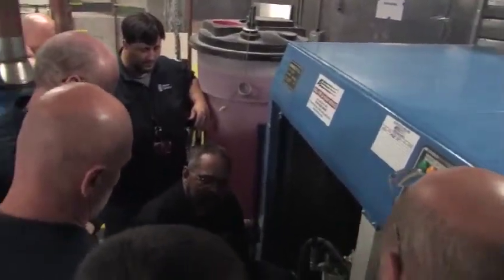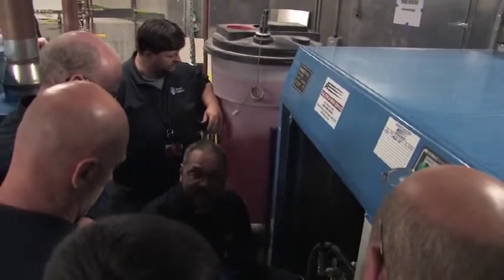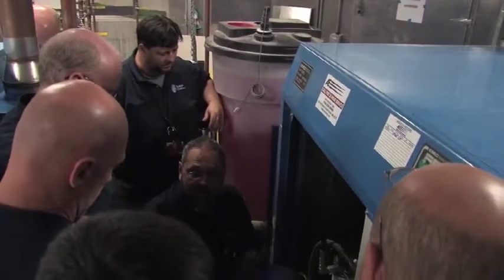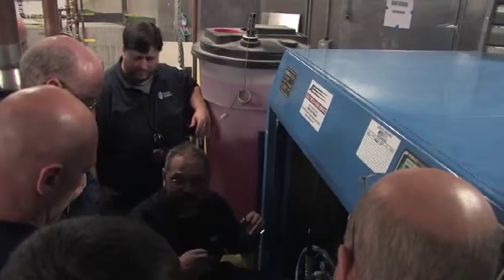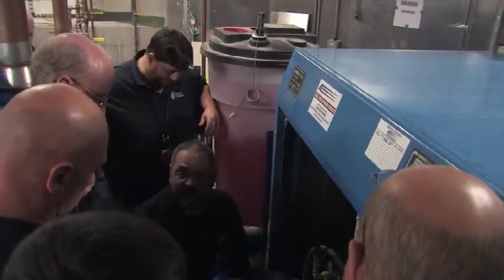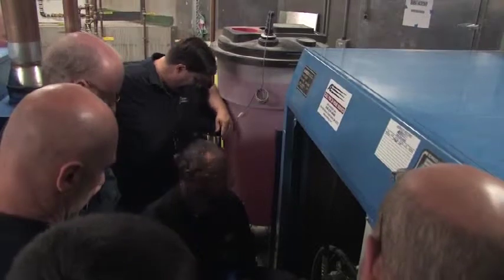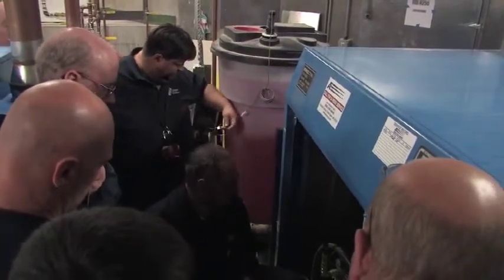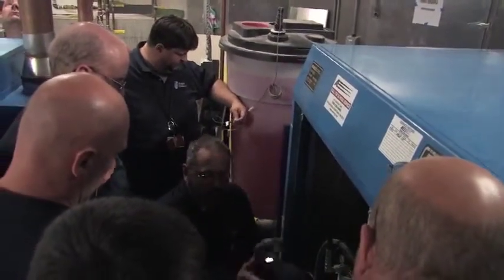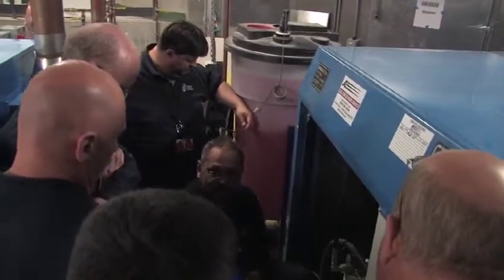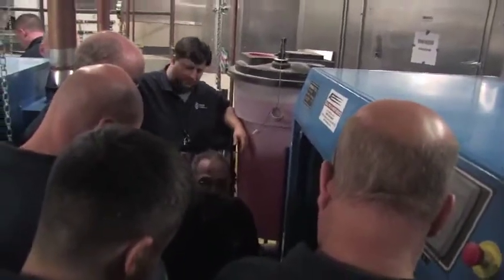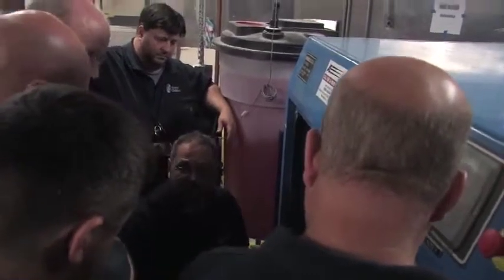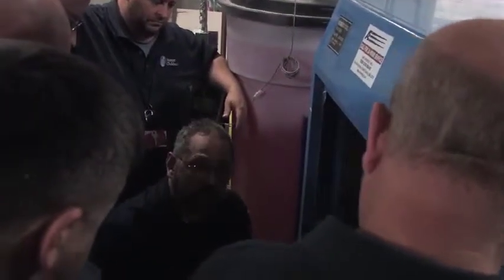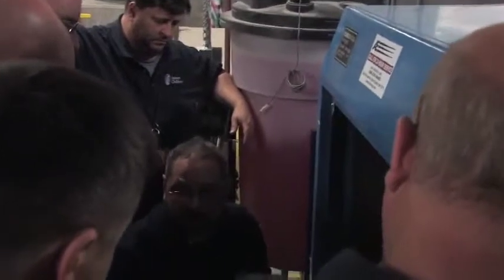But the important thing to remember about that, even if you're not relying on it, is that lots of times if you've got flaky power, a lot of phase monitors will trip out if the voltage goes off by 5%. So a lot of places get driven nuts by the phase monitors, and they jump them out anyway. The important thing to know is if you ever happen to change a motor or do something, or the power company did anything, and you have any thought that they might have reversed the phases, check the machine very carefully, and obviously everything in the machine is in the same phase. So if you test the cooling fan or the oil pump and it's going the right way, you're good. But the important thing is never run them backwards.